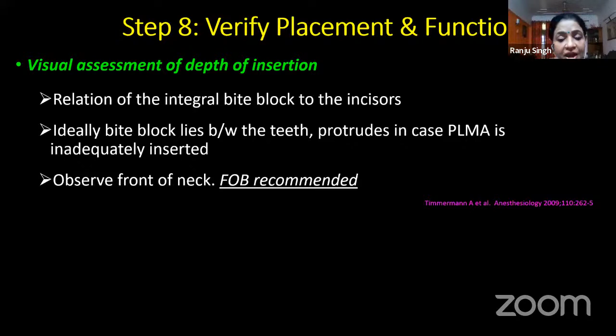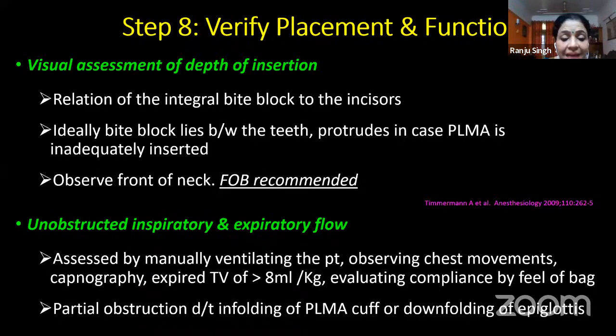Put the patient on a ventilator and check for the inspiratory and expiratory flows. You can also do that by manually ventilating the patient, observing the chest movements, looking at the ETCO2 graph, and looking for the compliance of the bag if you're manually ventilating. Keep a check of the tidal volume. The inspired tidal volume must be equal to the expired tidal volume. If that doesn't happen, that means there is some obstruction somewhere.